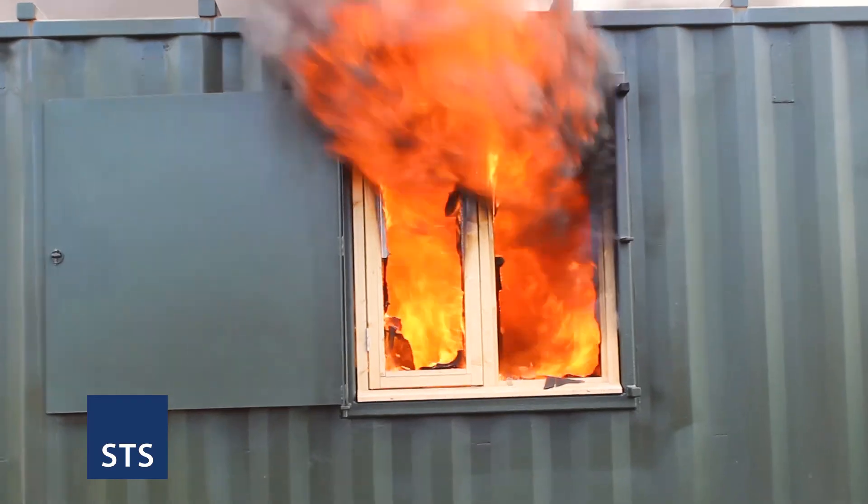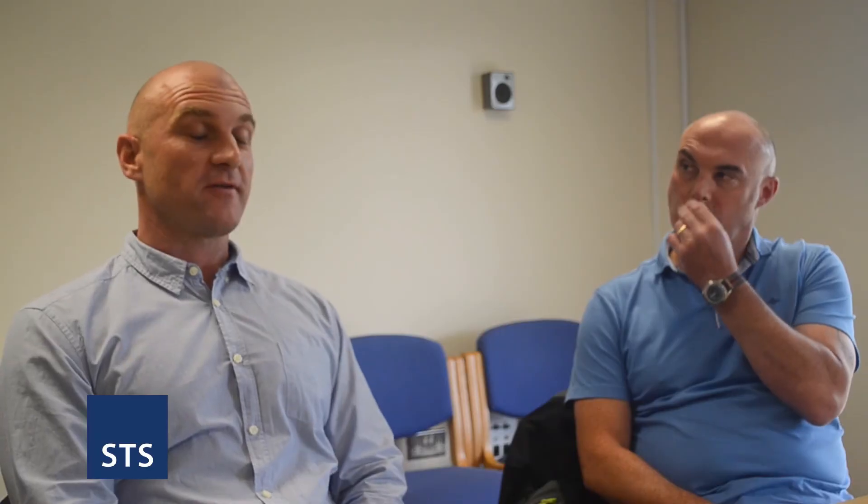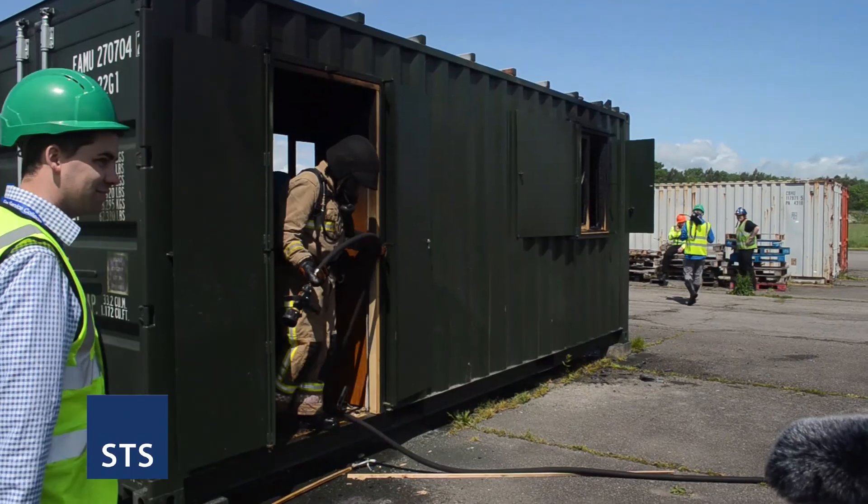Closure boards are good — they do prevent fire spread — but once they've obviously failed and exposed the underside of a timber floor, those timbers are then going to be attacked by the fire, which can promote further fire spread. From a firefighting point of view, boards that are staying in situ can only be a good thing, because they're not exposing the underside of whatever they're protecting — whether it be the ceiling or the wall — and they're not hindering the firefighters in any way.